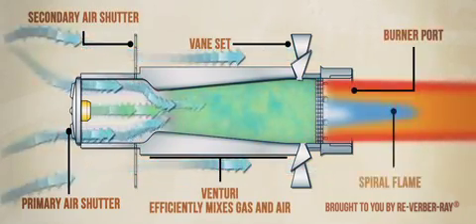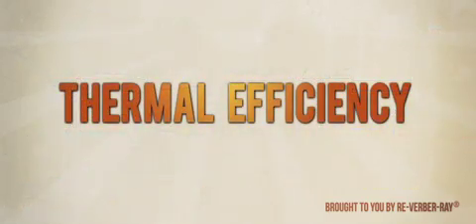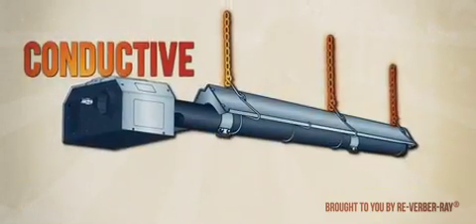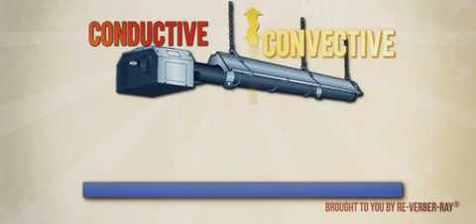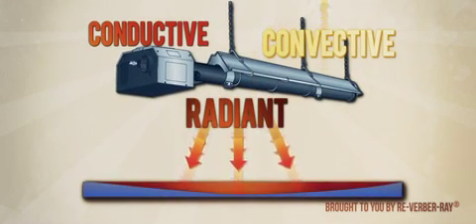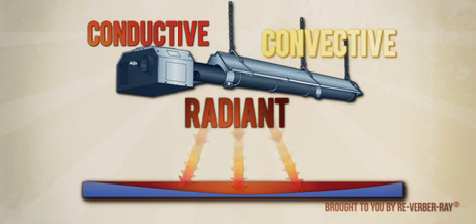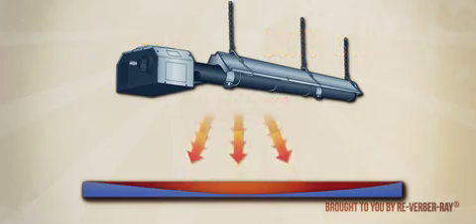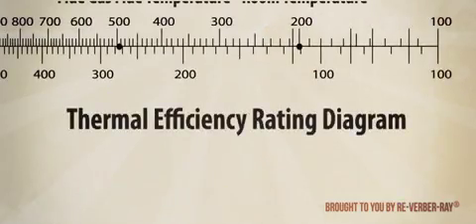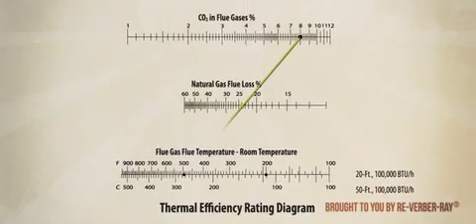Thermal efficiency is the measure of all energy – conductive, convective, and radiant – captured by the heater which is available for useful output. A well-designed infrared heater maximizes radiant output while minimizing convection and conduction thermal movements. Thermal efficiency is currently the industry standard for measuring the efficiency of an infrared heater in North America.